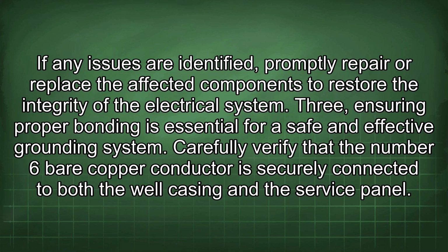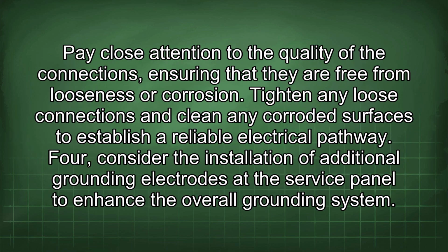3. Ensuring proper bonding is essential for a safe and effective grounding system. Carefully verify that the number 6 bare copper conductor is securely connected to both the well casing and the service panel. Pay close attention to the quality of the connections, ensuring that they are free from looseness or corrosion. Tighten any loose connections and clean any corroded surfaces to establish a reliable electrical pathway.